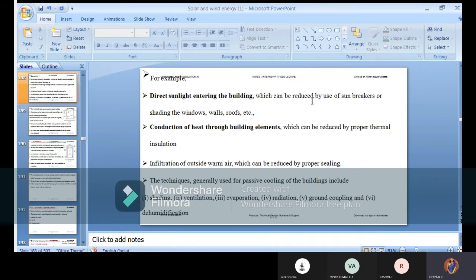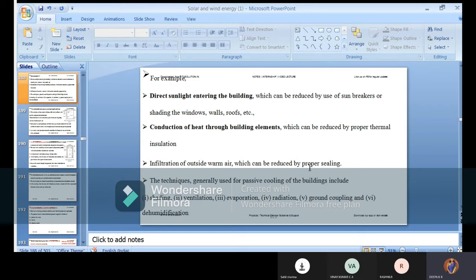Direct sunlight entering the building can be reduced by use of sunbreakers or shading the windows, walls, or roofs — similar to how trees provide shade. Windows should oppose the radiation-receiving direction. Roofs with certain inclinations reduce heat entry; houses typically leave a little overhang at the front, like car sheds or bike sheds, to reduce warm air entering. Conduction of heat through building elements can be reduced by proper thermal insulation. Infiltration of outside warm air can be reduced by proper sealing of the building.